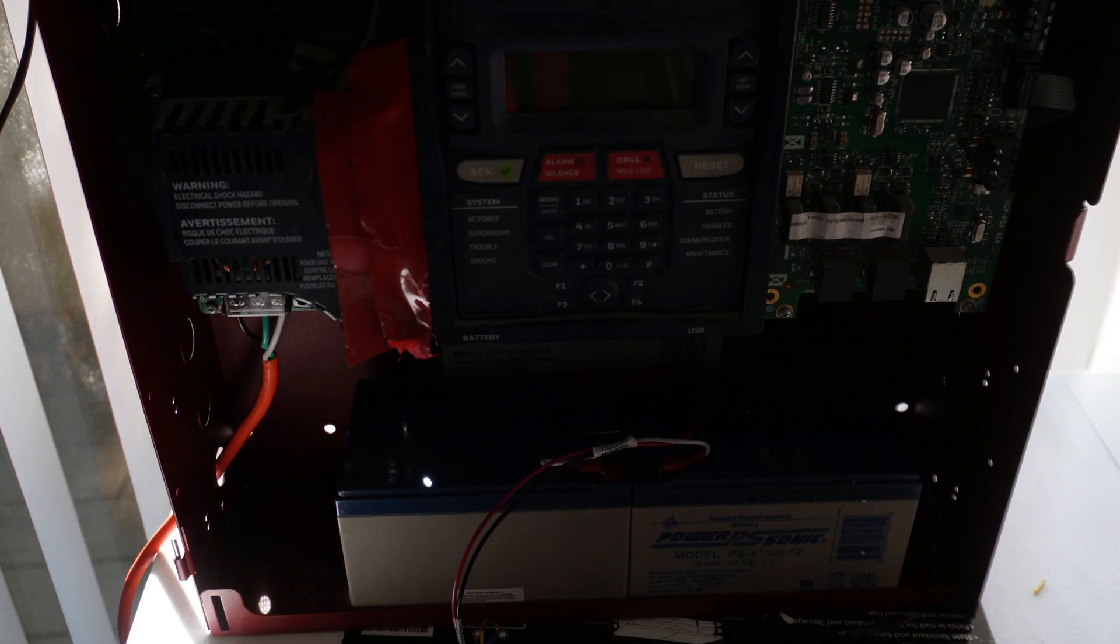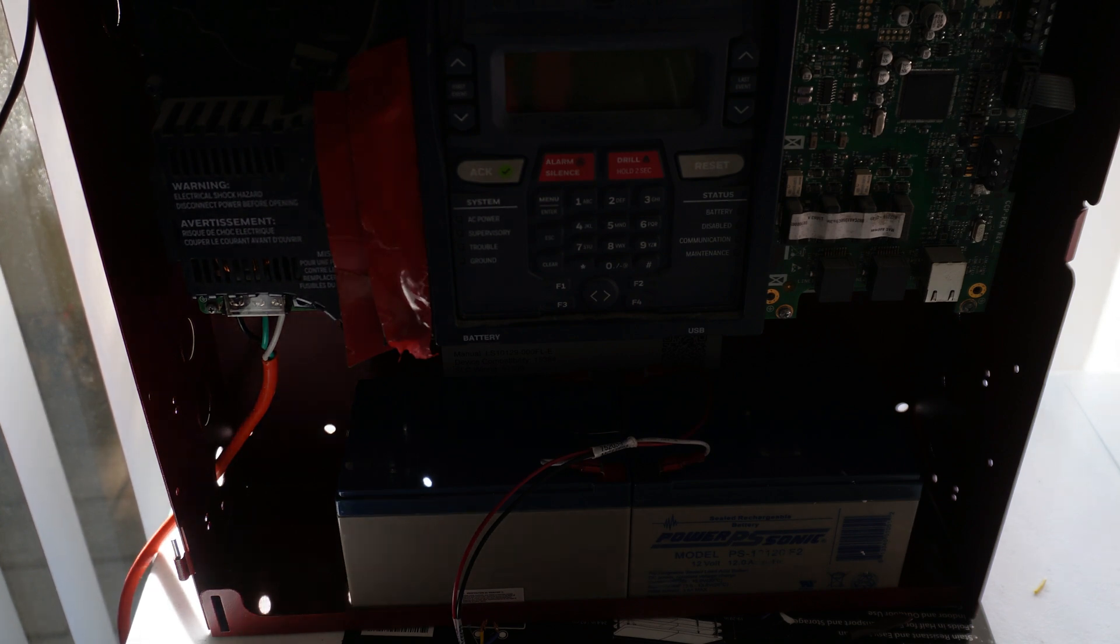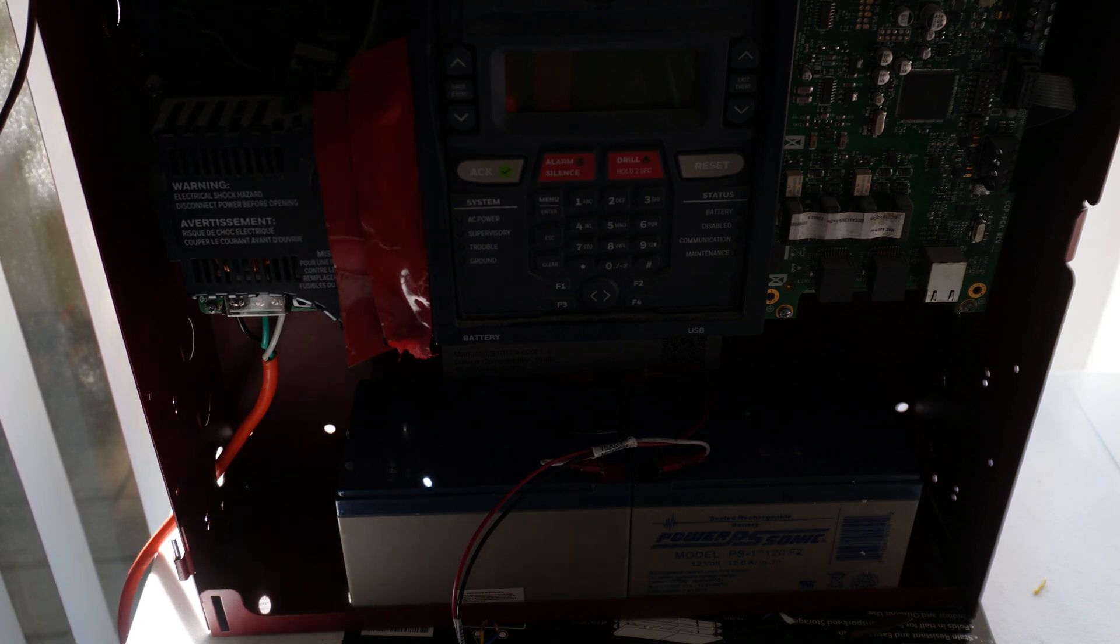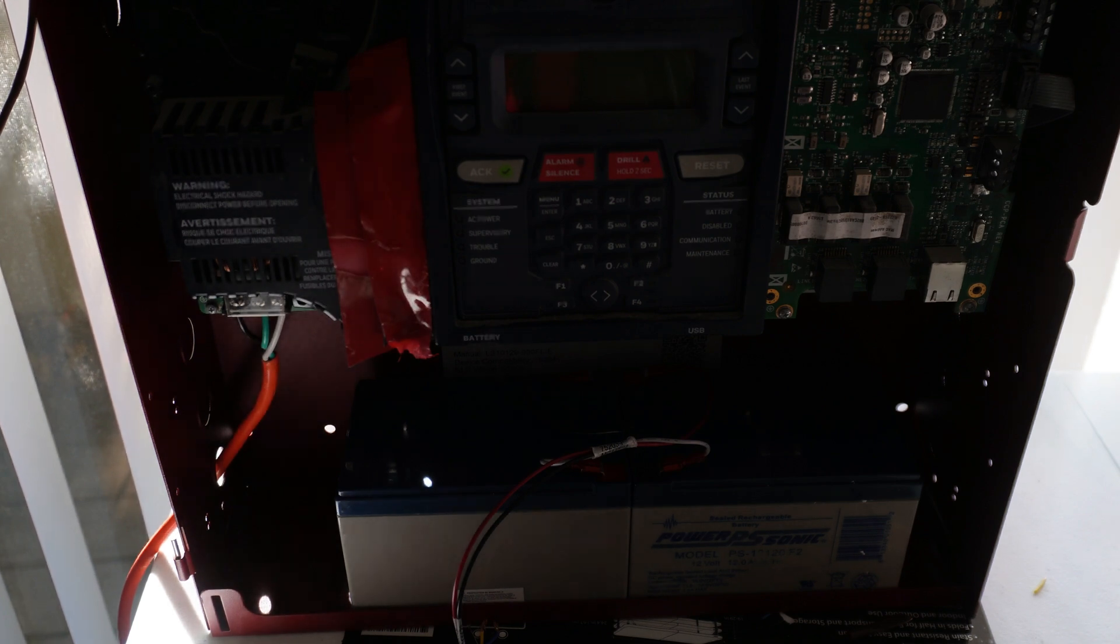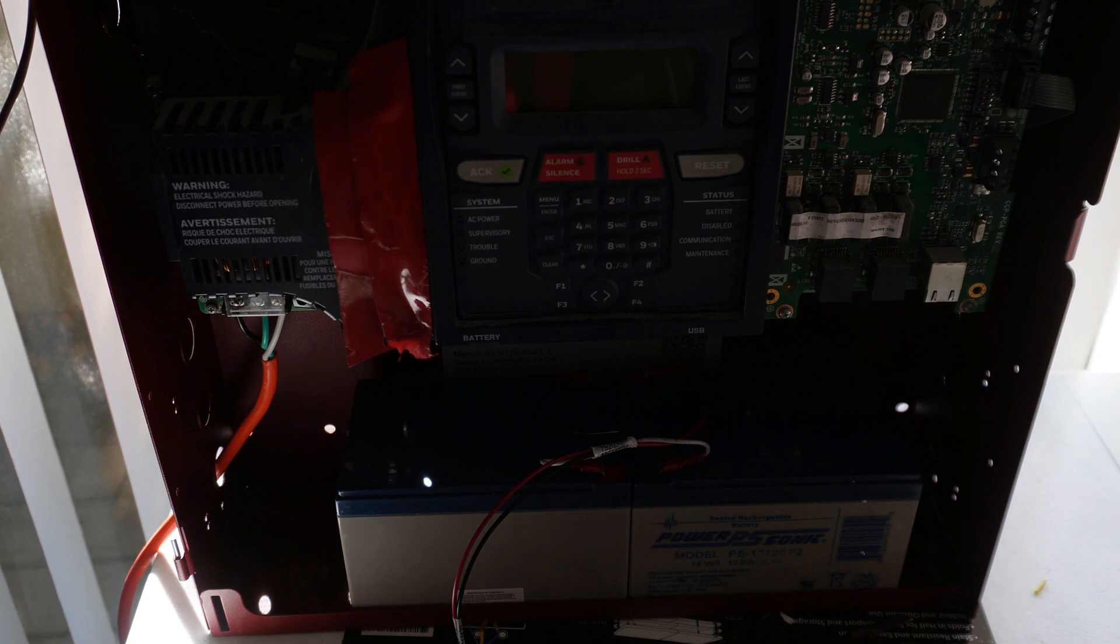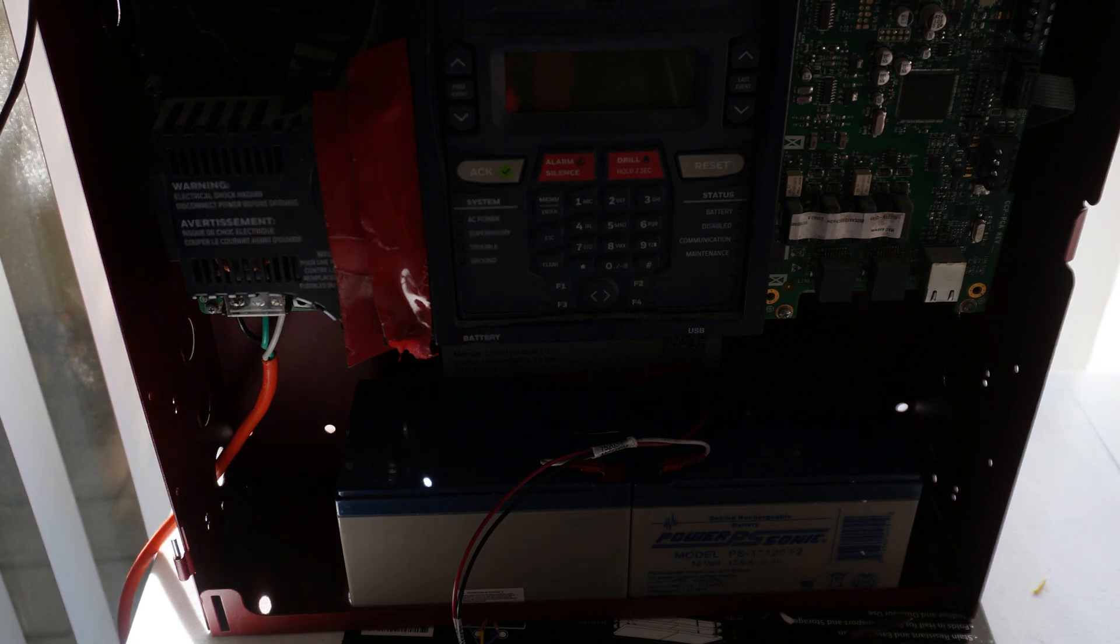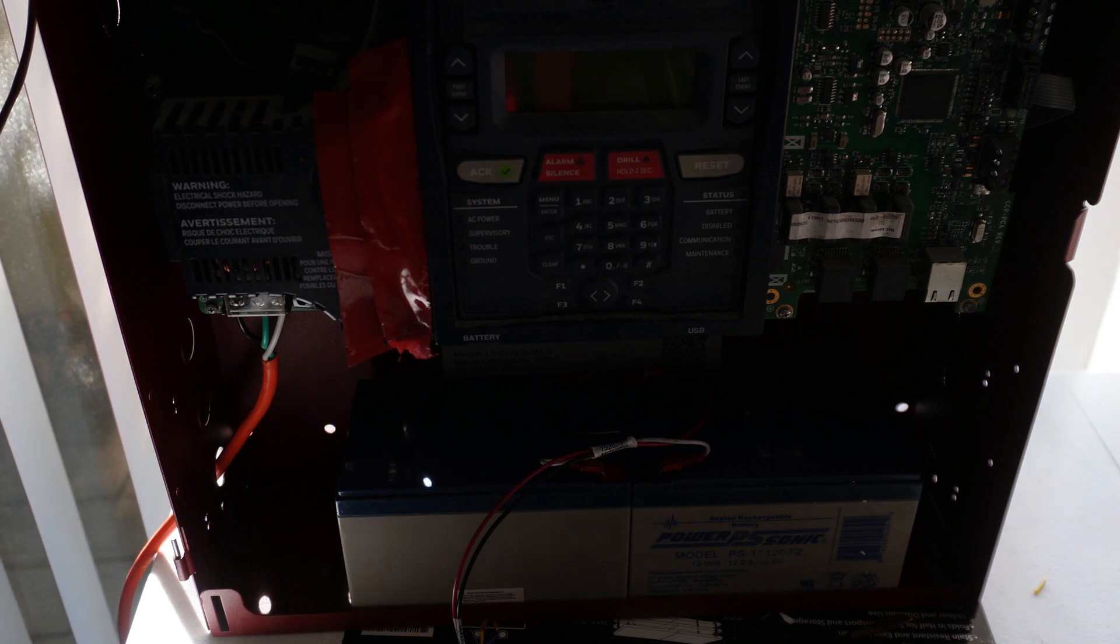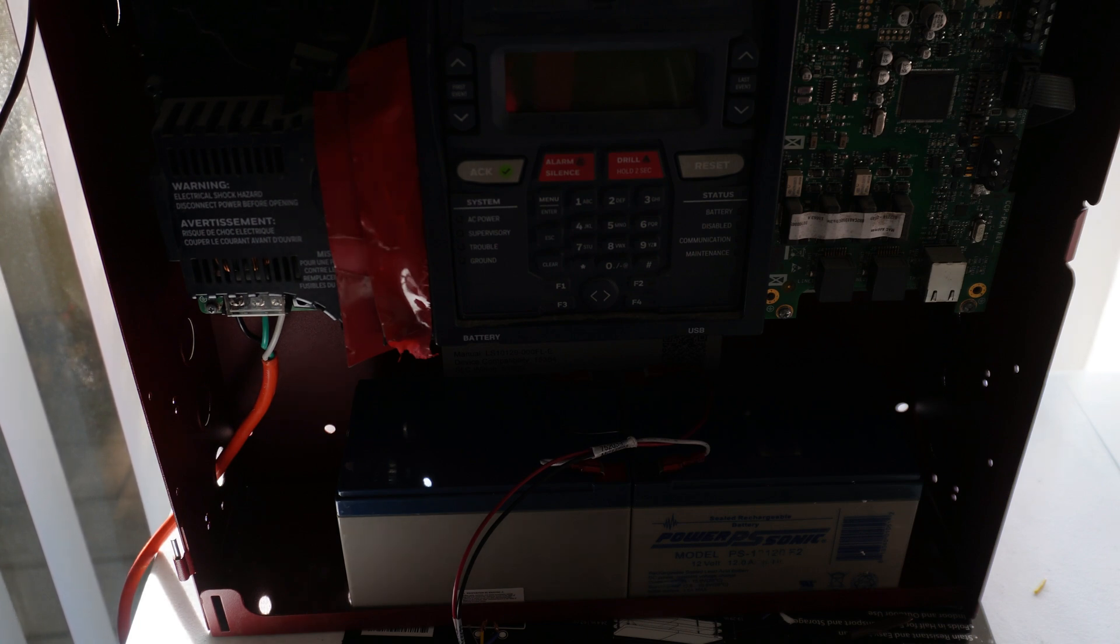First, before we do any of that, we need to make sure the system is powered down just like last time before changing any of the wiring configuration. I disconnected the battery of the alarm panel and then I cut the AC power and the system is shut down. Always be sure that the system is shut down completely before changing any wiring configuration.